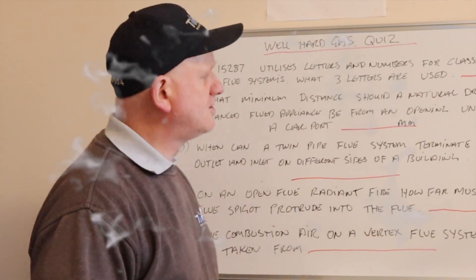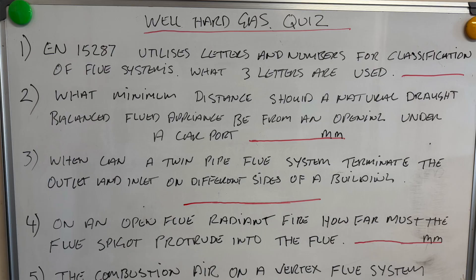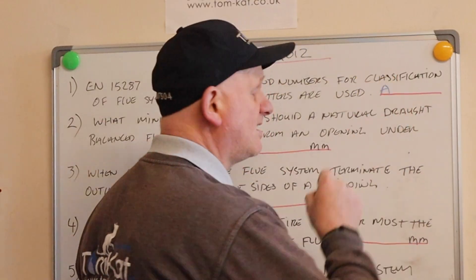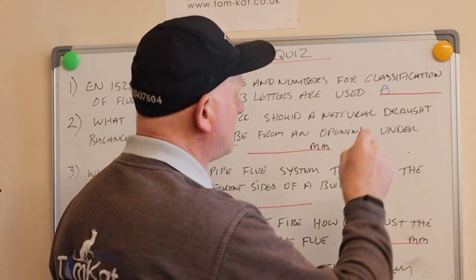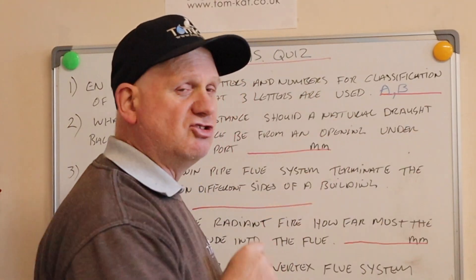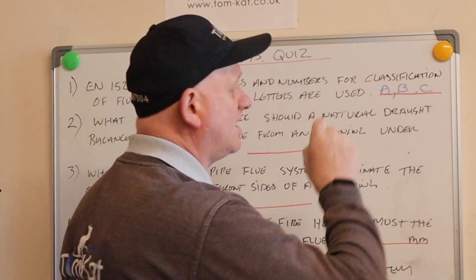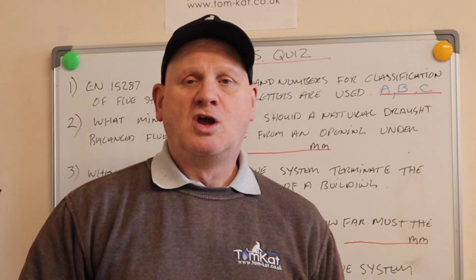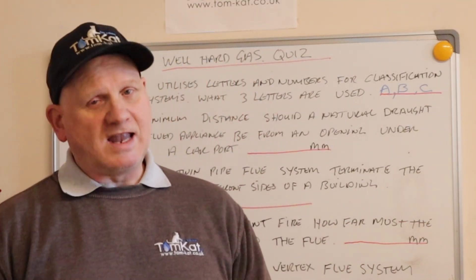Question number one: EN 15287 utilizes letters and numbers for the classification of flue systems. What three letters are used? Letter A is used for flueless appliances, letter B is used for open flued appliances, and letter C is used for room sealed appliances.